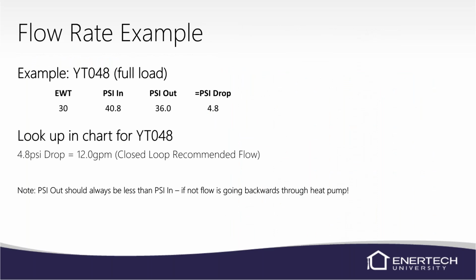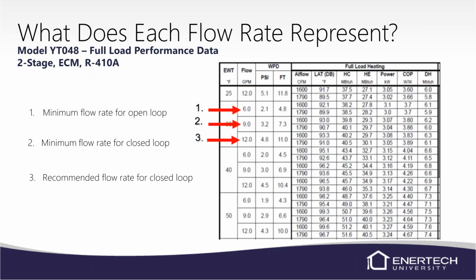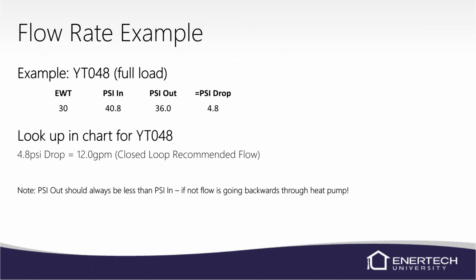So we'll do a little quick flow rate example. So if we've got a YT 048, 30 degree entering water temperature, 40.8 PSI in and 36 out. So 40.8 minus 36 is 4.8. So if we look in a chart, 4.8, we take the PSI, not the feet of head, take the PSI pressure drop at 30 degrees, and that tells us we have 12 GPM. So don't just guess that you've got 12 GPM going through there. Do the pressure drop so we know what we've actually got.